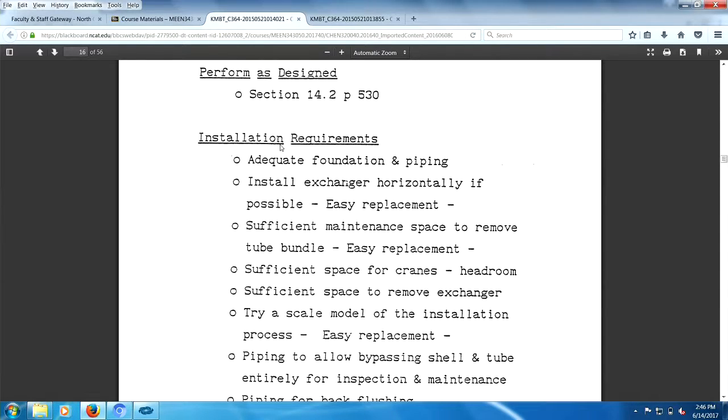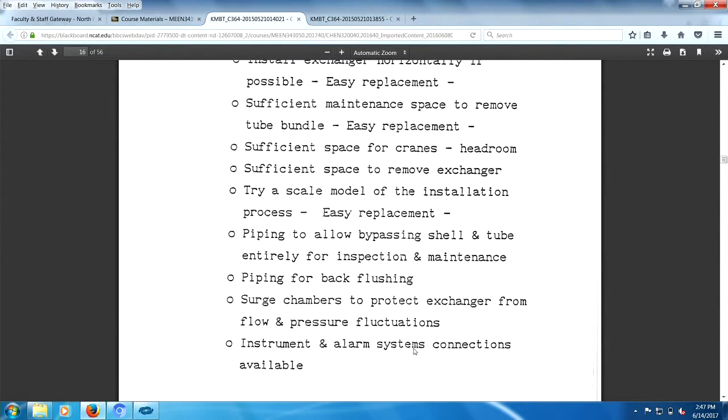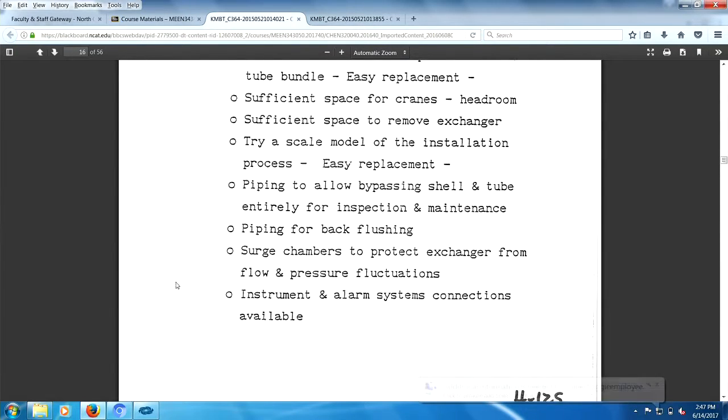Installation: adequate foundation, piping installed horizontally, easy replacement when that's done. Sufficient maintenance space to remove the tube bundle, cranes for headroom, sufficient space to remove the heat exchanger. You might do a scale model of the piping, allow bypassing the streams for easy inspection and maintenance.